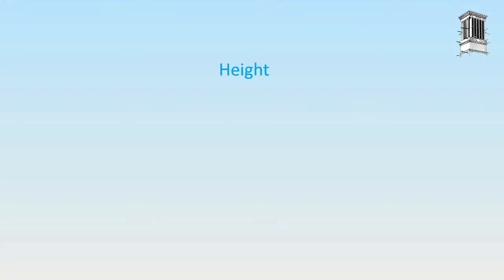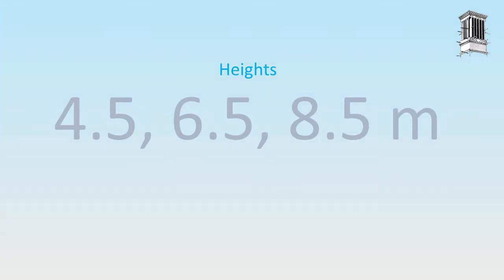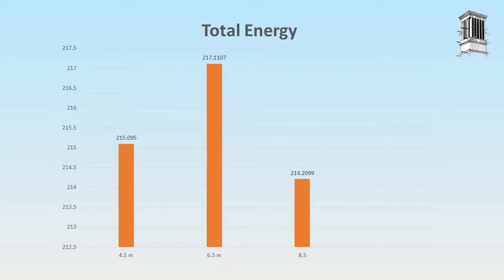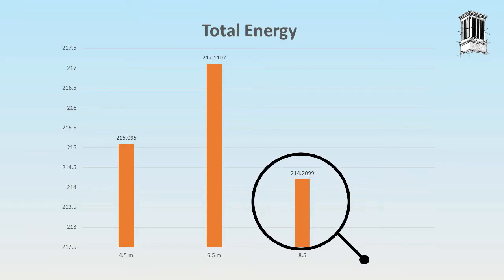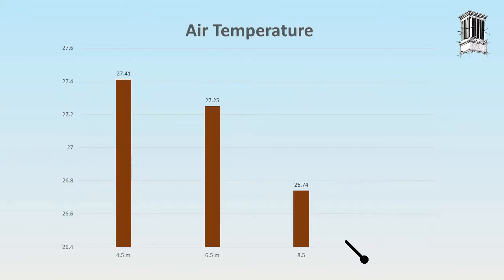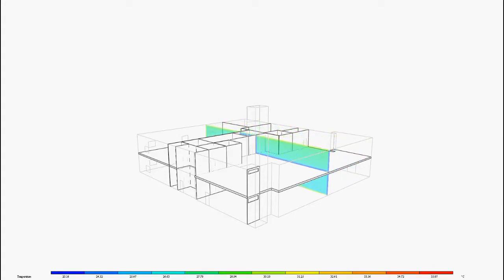The first 3 scenarios examine 3 different heights, which are 4.5, 6.5, and 8.5, in which they are based on the literature. According to the literature, the higher the wind catcher, the better performance it has. In my study, the results show that among the 3 wind catchers, the highest one has the lowest energy consumption, which is 214 megawatt hour, and low air temperature with the mean of 26.7 degrees, which shows that my results align with the literature.